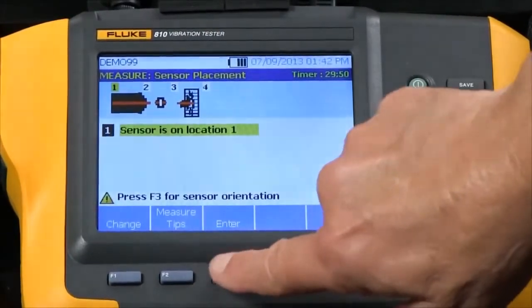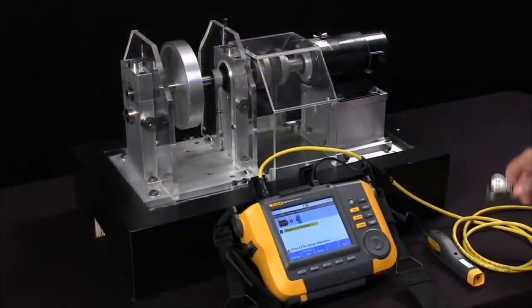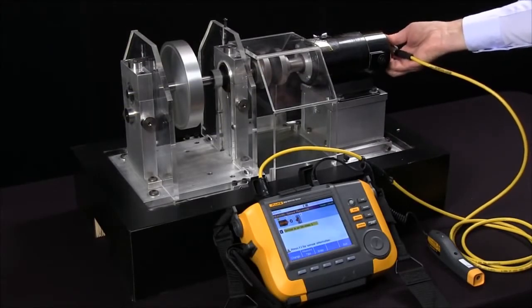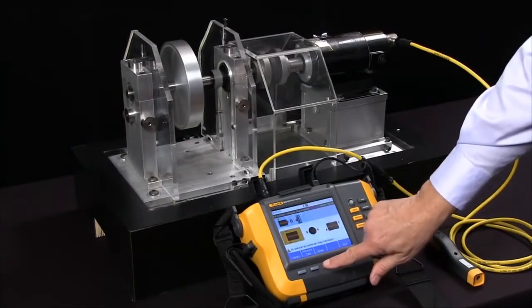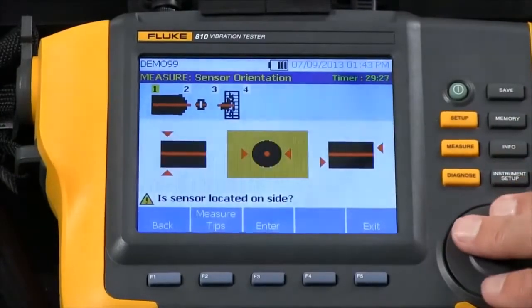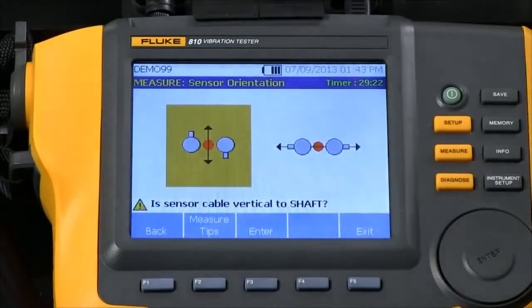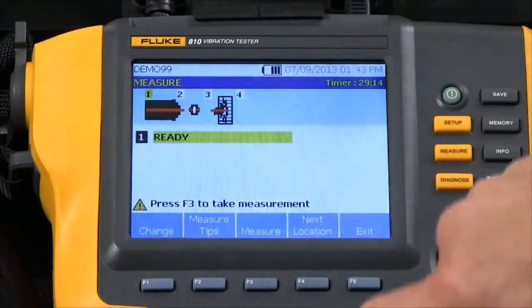I hit enter and it says 'sensors on location 1,' so it wants me to put the sensor on the free end of the motor. I rotate the magnetic mount onto the motor housing and press enter. Now it wants to know: is it on the top, the side, or the end?